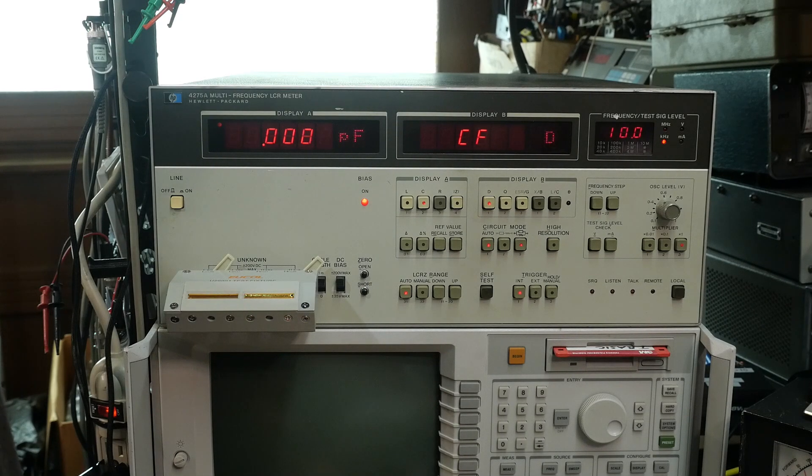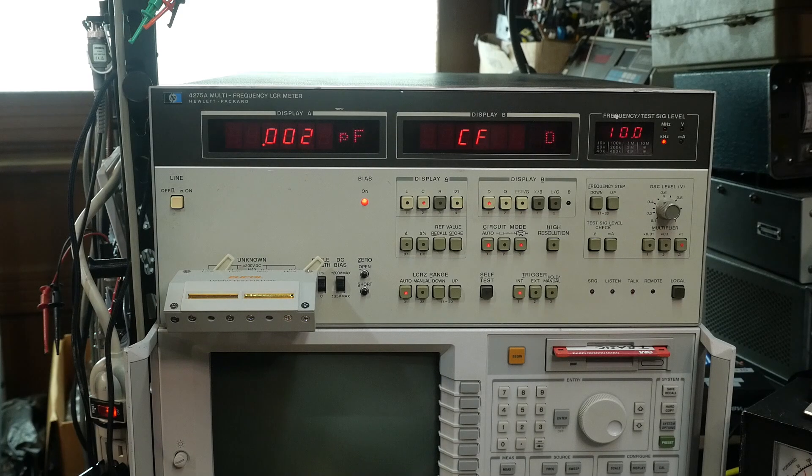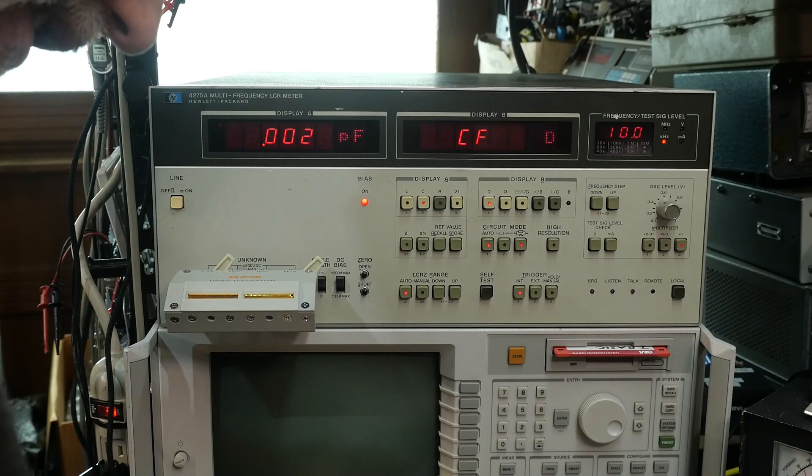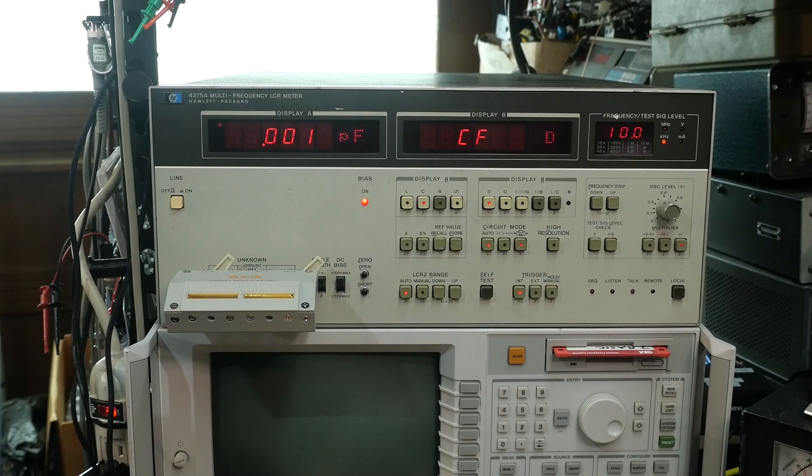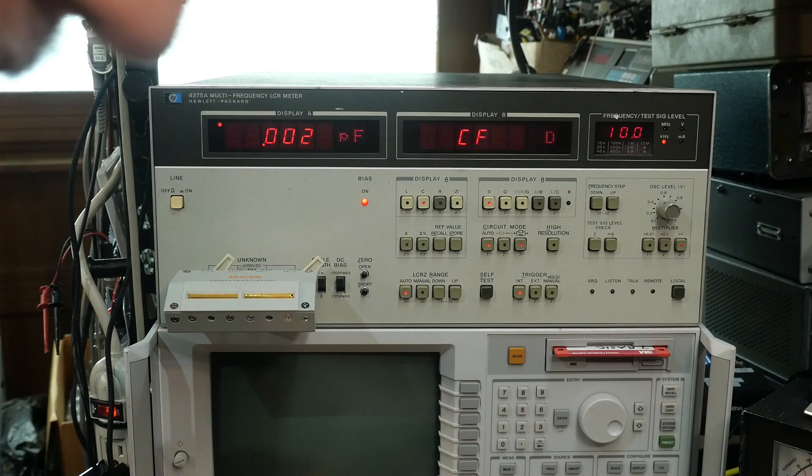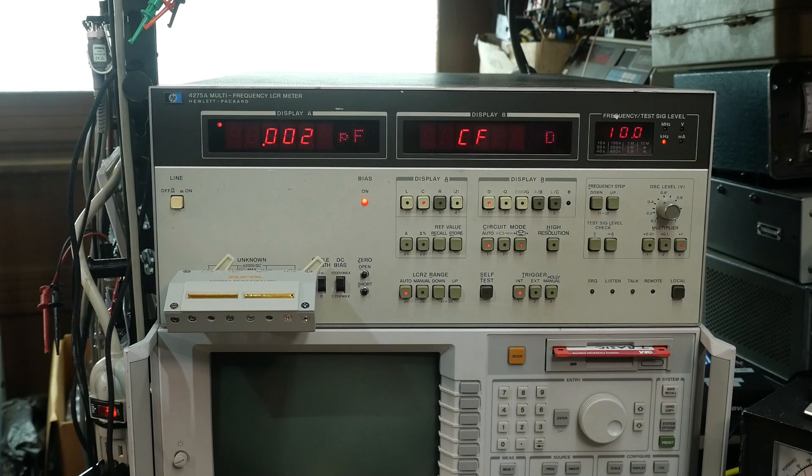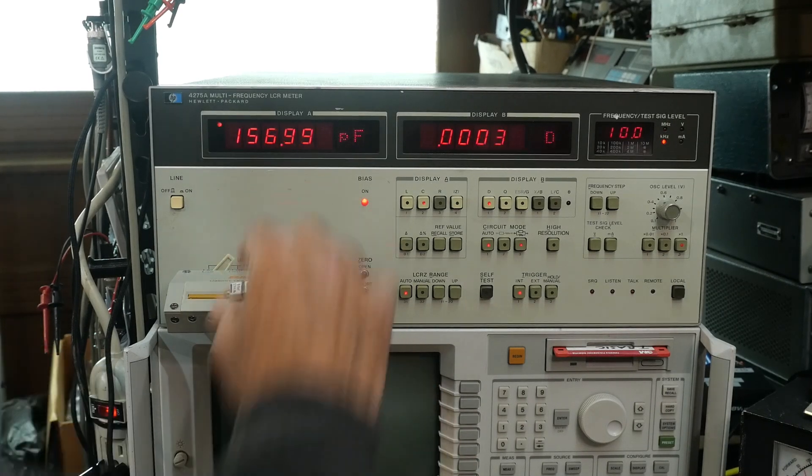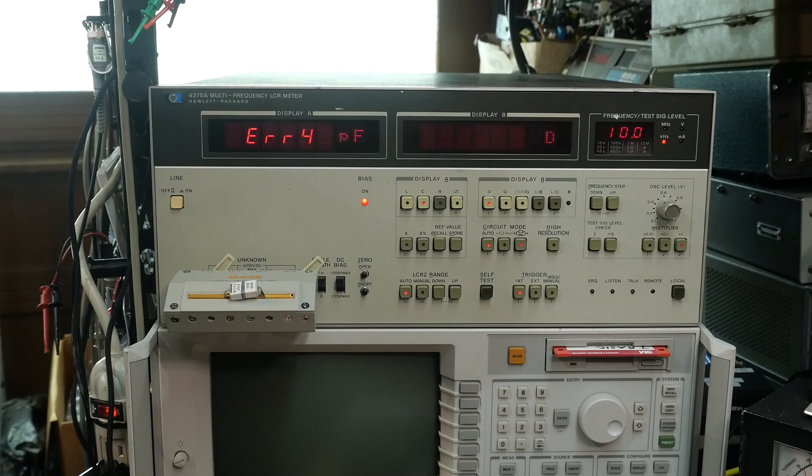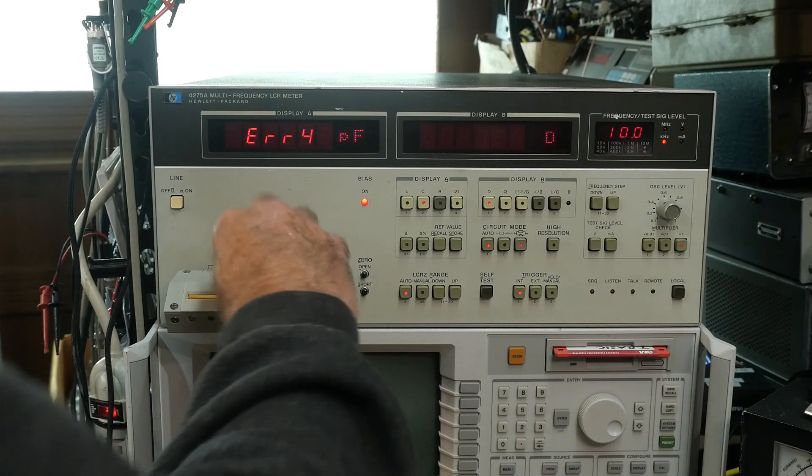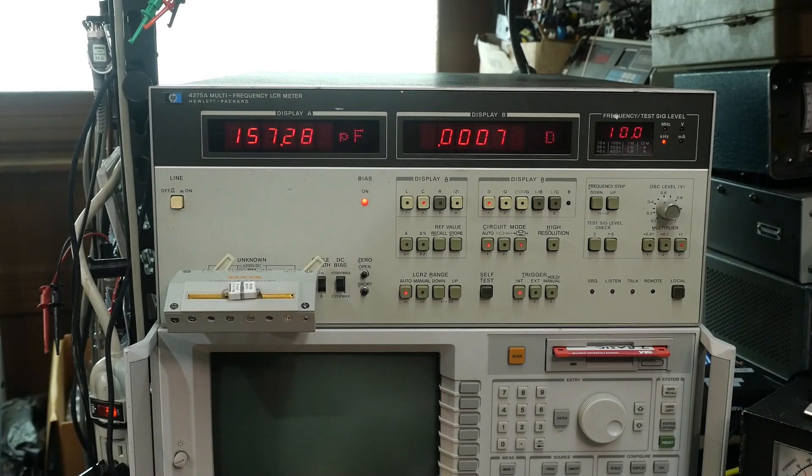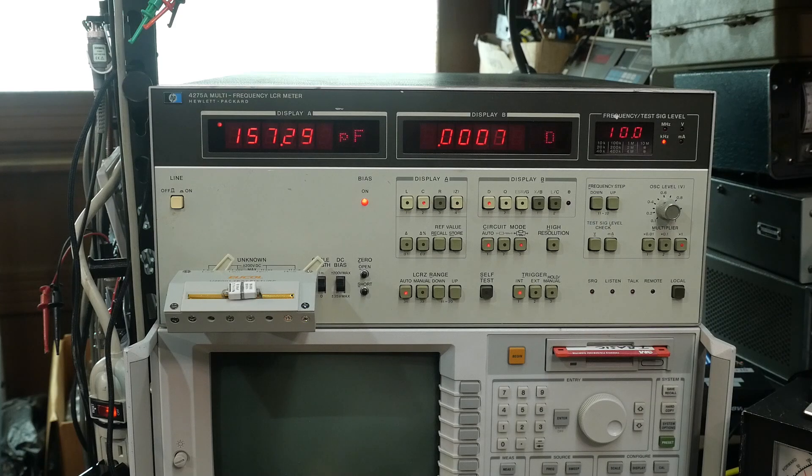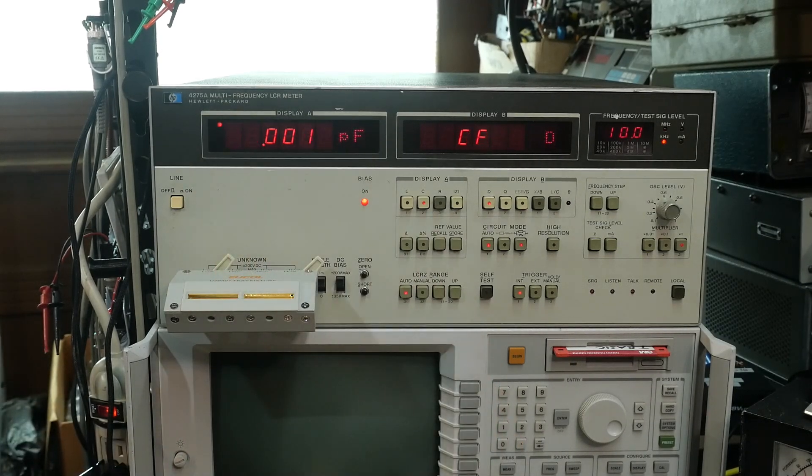And we are zeroed at .002 picofarads. Not too bad. All right. And let's put in some capacitor. Just had it in my hand. What did I do with it? All right. Let's pop this in. This is 158 picofarads. 157.26. Close enough. All right. So the thing's up and running again.